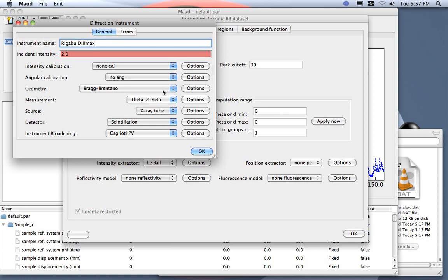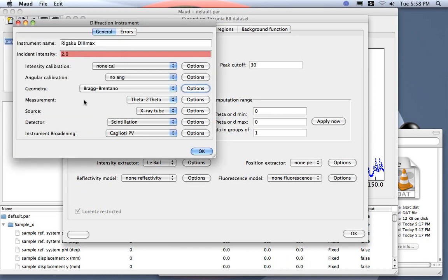The geometry is Bragg-Brentano. There are some options. Well, you can put, okay, the radius of this one was 183 millimeter. Okay, and the second arm was having a monochromator. The angle, let's see if I remember it, it is a graphite monochromator, something around 24 degrees. Okay, it doesn't matter, it only changes a little bit the Lorentz polarization factor.